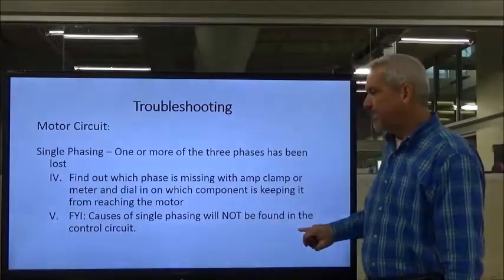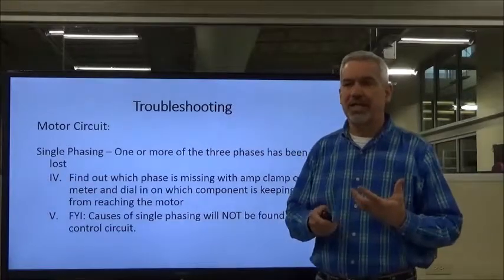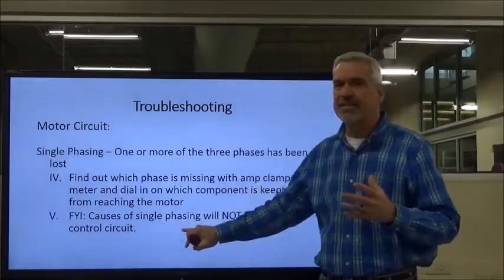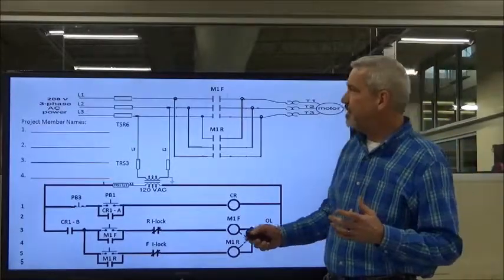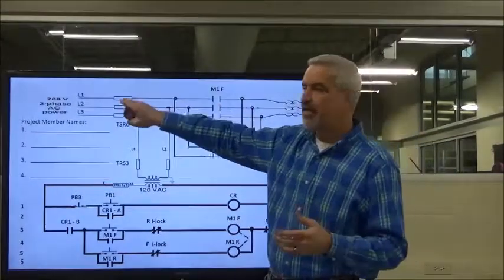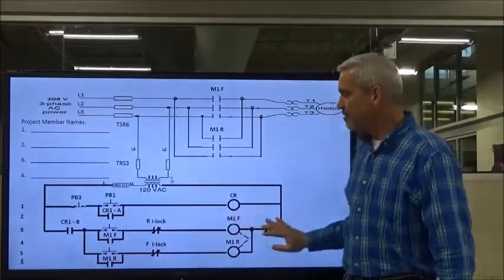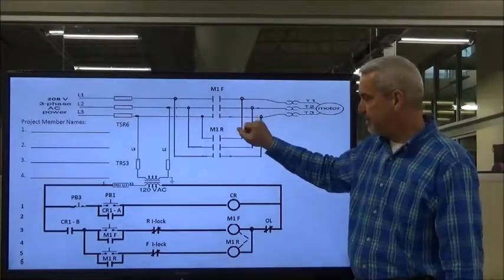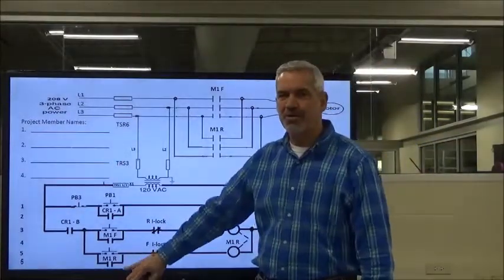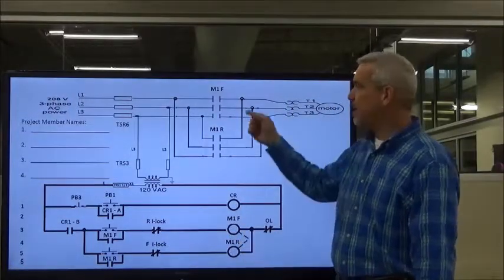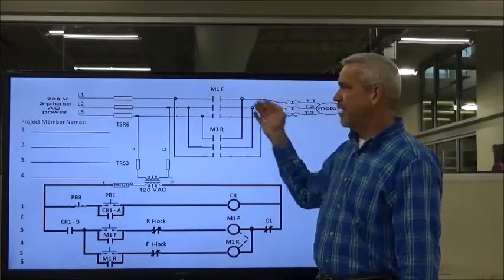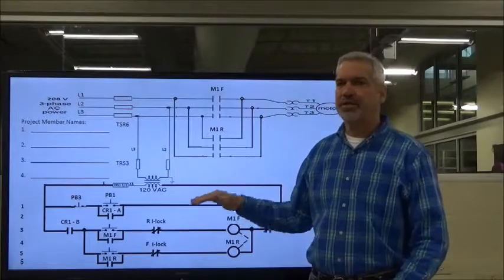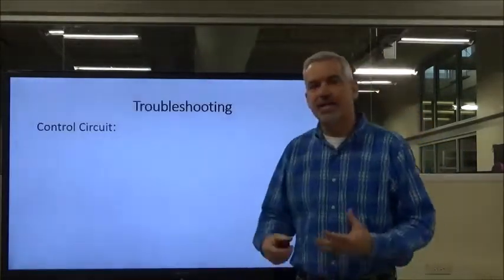Here's another important point: when you have a single-phasing situation, you're not going to find the problem in the control circuit. I lost one of my phases — there is no component in the control circuit that's causing me to lose one of three phases. When you have a motor single-phasing, don't even worry about the control circuit. We know the control circuit is working because it's trying to bring the motor in and close the contacts. Only one or two phases are getting to the motor, but we know the control circuit is okay. The control circuit has nothing to do with the single-phase situation.